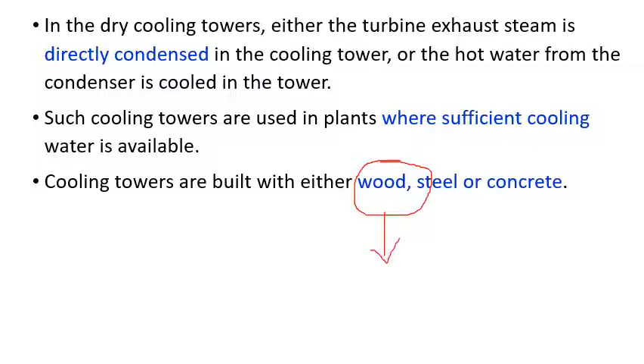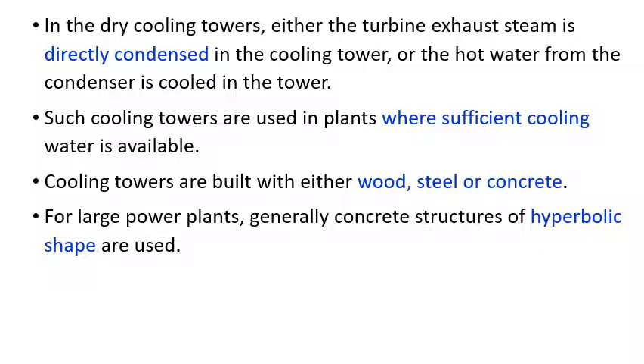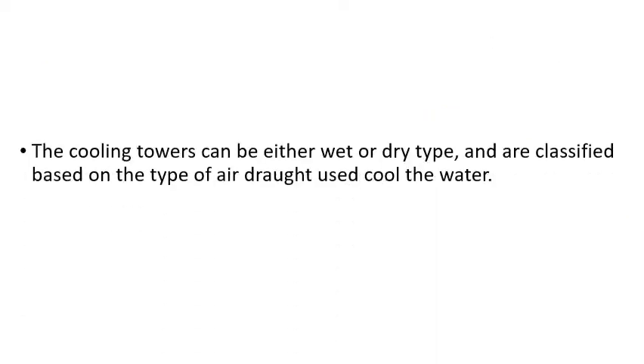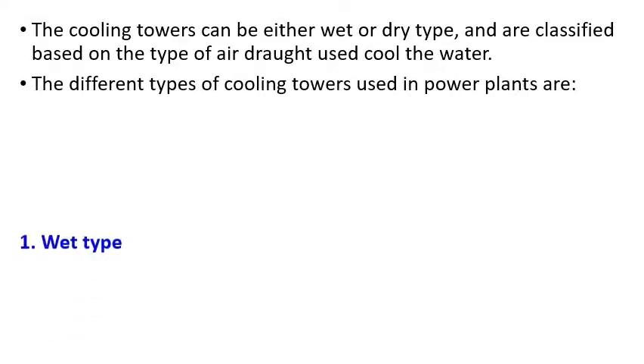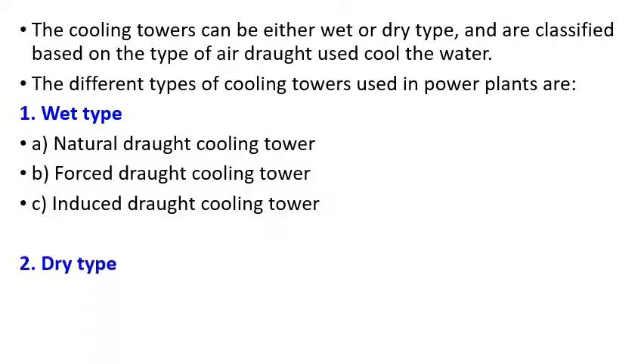The material used for construction should be teak wood or a better composite material, which has now replaced wood. Steel and concrete are also used. Large power plants generally have a hyperbolic structure because it provides sufficient cooling and high cooling capacity. Cooling towers, whether wet or dry, are classified as: wet type — natural draft, forced draft, and induced draft; and dry type — direct and indirect.